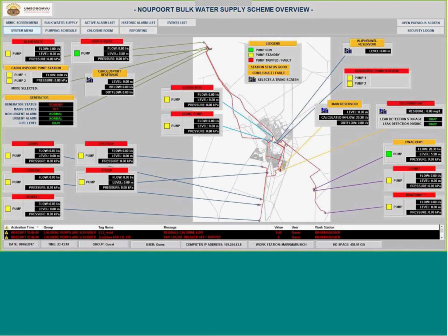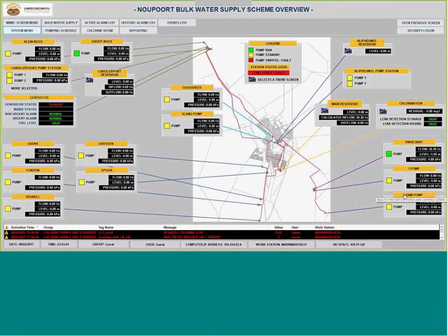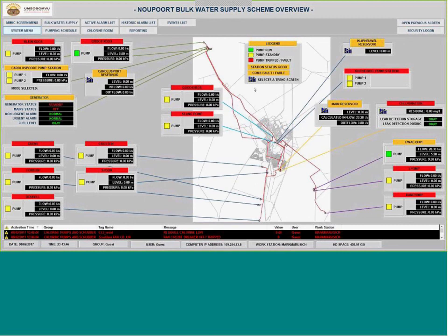And I agree with it because it's less of an issue for us to create this kind of thing. It sometimes does look a little bit bland, but just looking at this overall screen here, I know exactly what is happening. There's a pump running over here. This pump is basically currently on standby, but there's possibly a communication error or whatever it is with these specific stations. And that is basically what the client and the user actually wants to see.